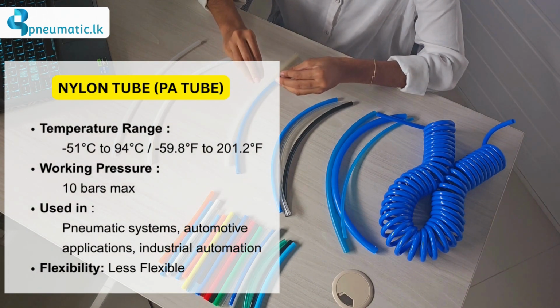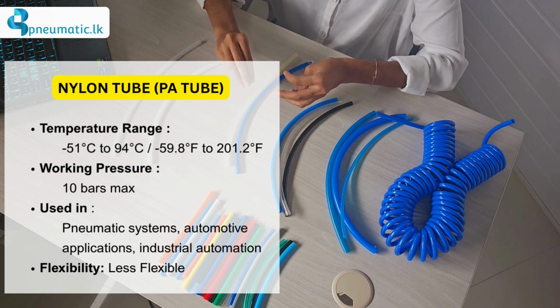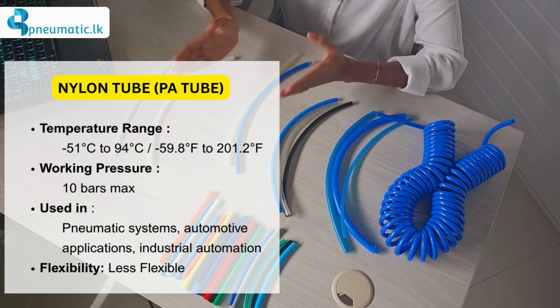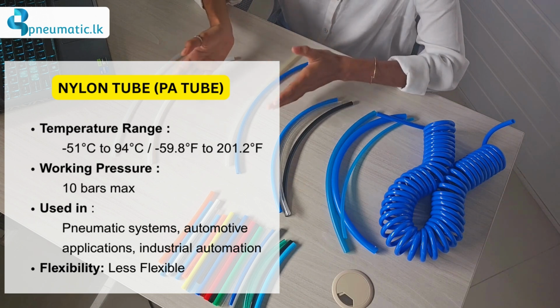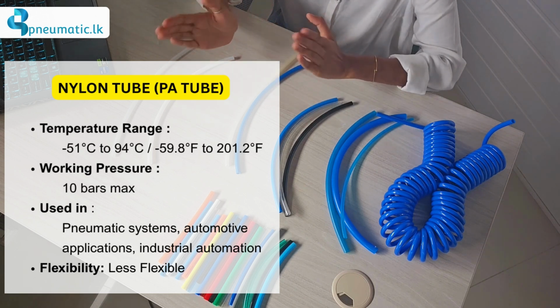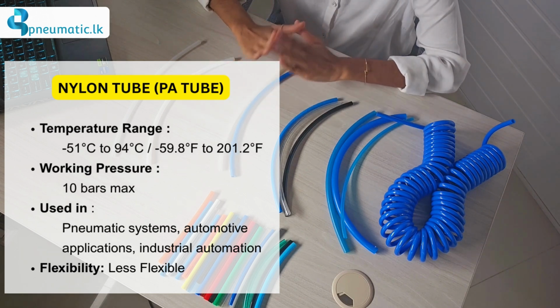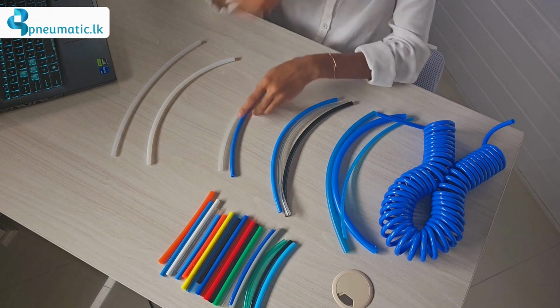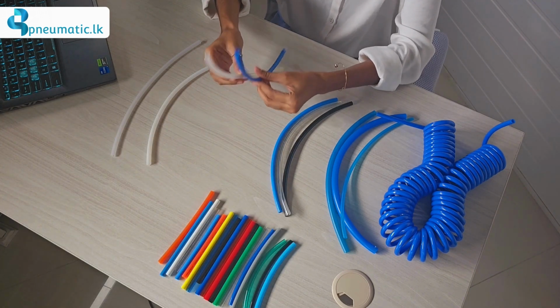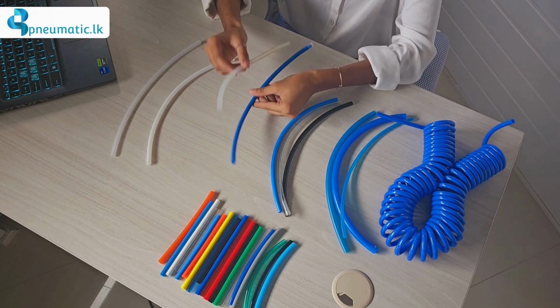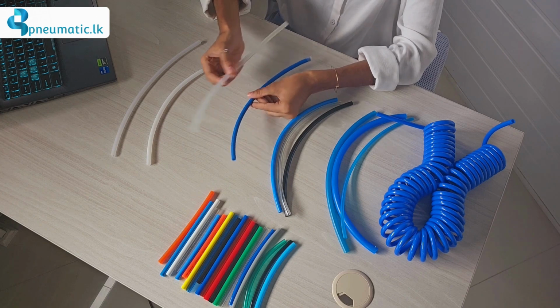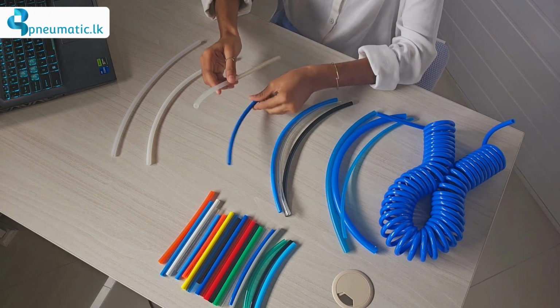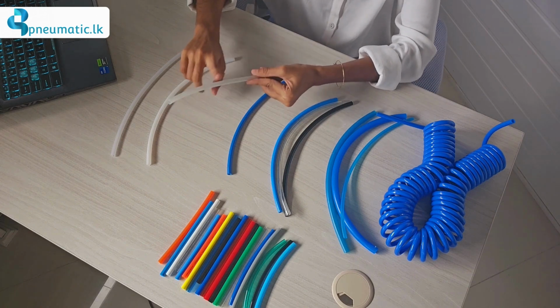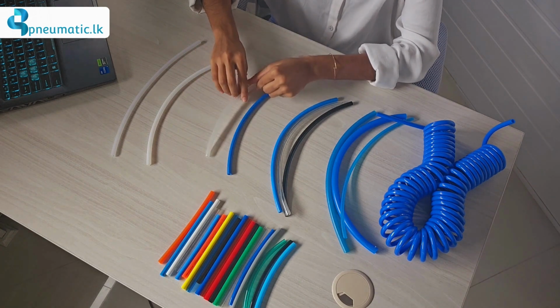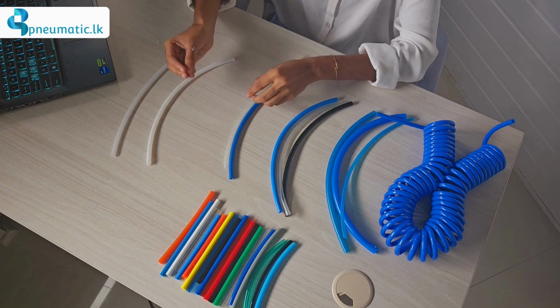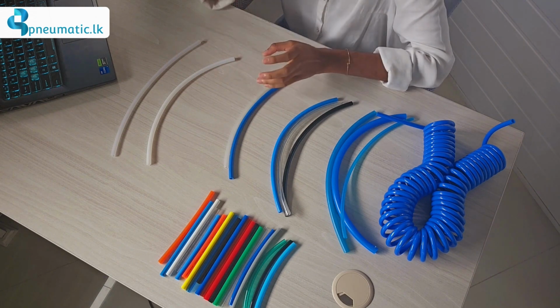The temperature tolerance of these tubes is between minus 51 Celsius and 94 Celsius. The pressure these tubes can handle is up to 10 bars. You can find PA nylon tubes in two different colors. One is off-white or pale white. The other one is blue. Most often, the pale white or off-white tubes are the ones used by most of the industries.